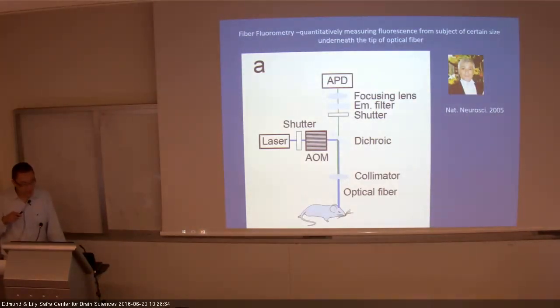Now, fiber fluorometry is a method for neuroscience, first developed by Helmut Adelsberger in the Cornet lab. The paper was published in 2005, but the experiment was done much earlier. So actually this happened, you need to keep in mind, before optogenetics and not after. So the laser is the light source for excitation. If you remember, fluorescence excitation needs a light. This light typically is blue, and it is modulated by an acousto-optic modulator. This changes the intensity of light, because you don't want very strong light illuminating all the time; you want to adjust the intensity.